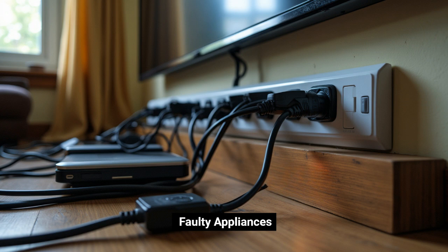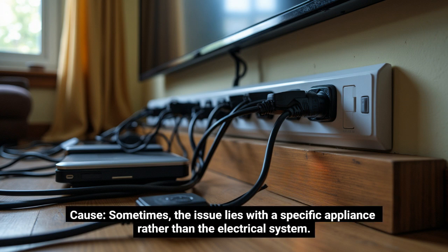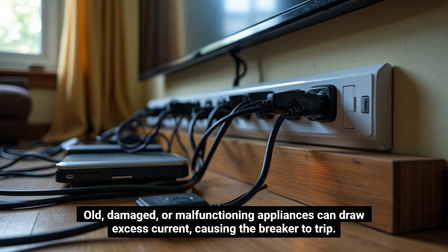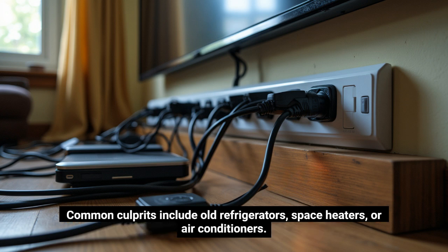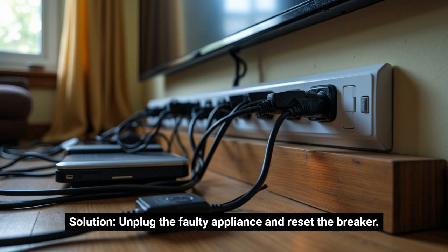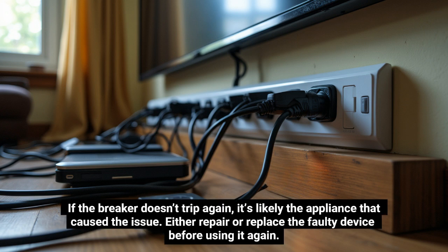Faulty appliances. Cause: sometimes, the issue lies with a specific appliance rather than the electrical system. Old, damaged, or malfunctioning appliances can draw excess current, causing the breaker to trip. Common culprits include old refrigerators, space heaters, or air conditioners. Solution: unplug the faulty appliance and reset the breaker. If the breaker doesn't trip again, it's likely the appliance that caused the issue. Either repair or replace the faulty device before using it again.